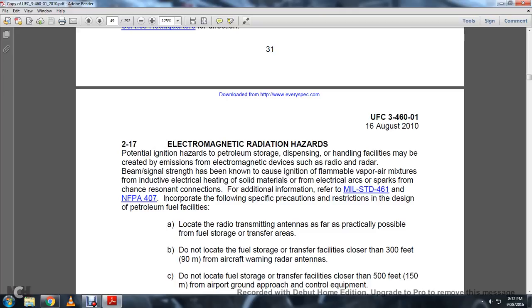All right, 2.17 Electromagnetic radiation hazard. Potential ignition hazards for petroleum storage, dispensing, and handling facilities may be created by the emission of electromagnetic devices such as radio or radar.